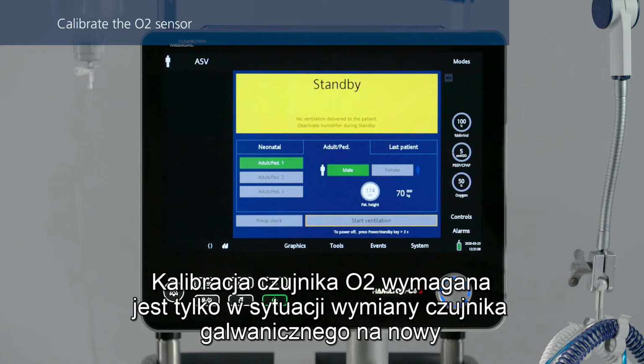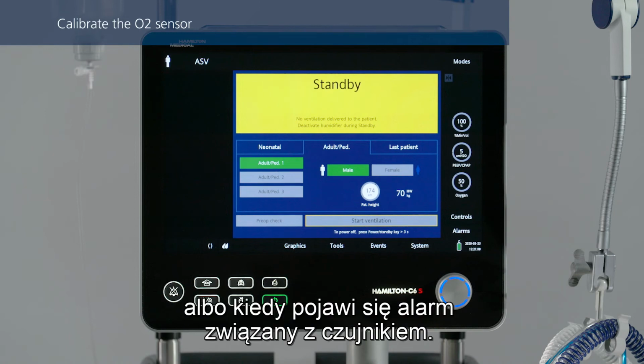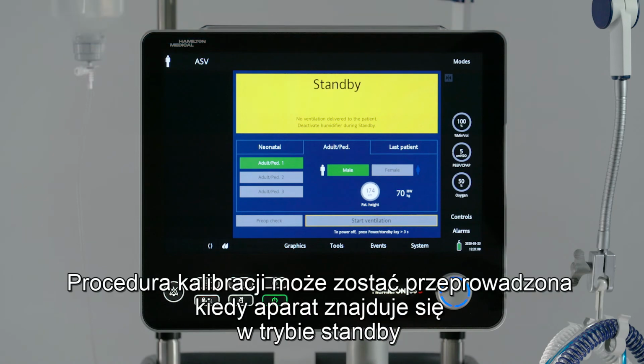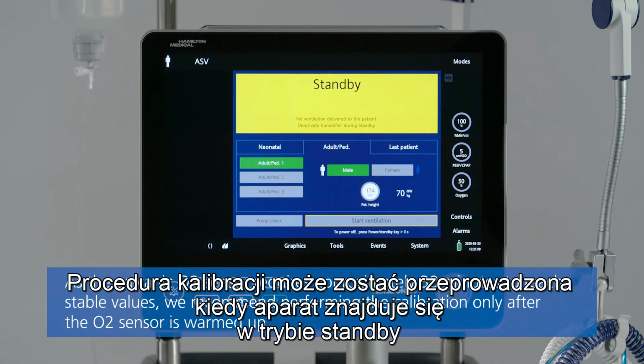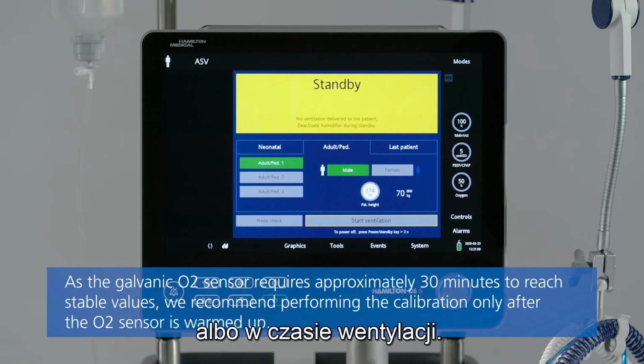Calibration of the oxygen sensor is only needed after installing a new galvanic oxygen sensor or when a related alarm occurs. The calibration procedure can either be performed when the ventilator is in standby or during active ventilation.